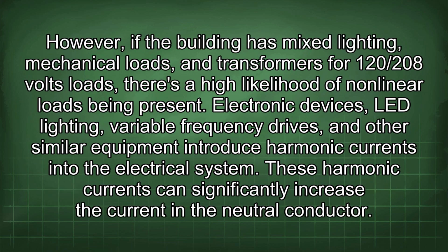However, if the building has mixed lighting, mechanical loads, and transformers for 120/208 volt loads, there's a high likelihood of nonlinear loads being present. Electronic devices, LED lighting, variable frequency drives, and other similar equipment introduce harmonic currents into the electrical system. These harmonic currents can significantly increase the current in the neutral conductor.